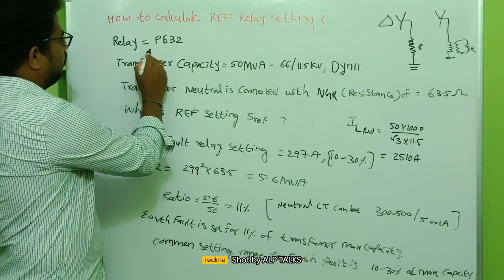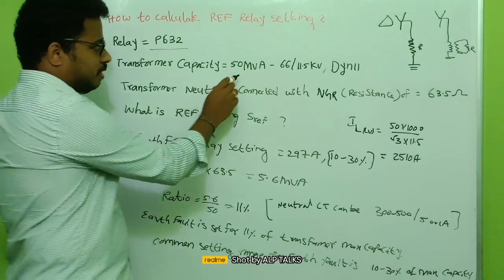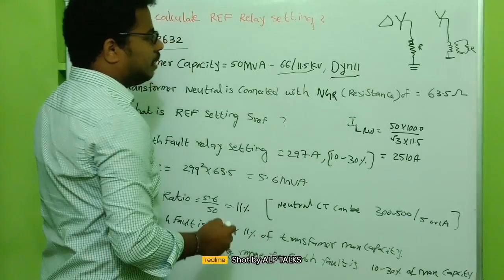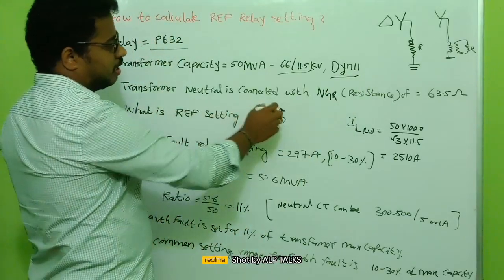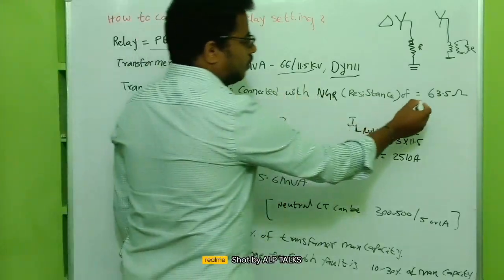The relay is P632 model, so the transformer capacity is 50 MVA and 66 by 11.5 kV, and it is of DYN11 vector group. The transformer neutral is connected with the NGR resistor of 63.5 ohm.